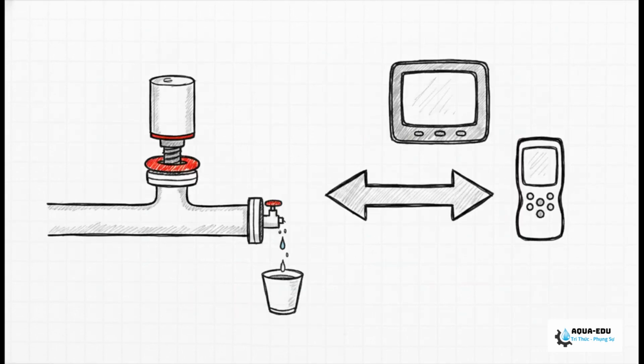Time to reinstall the probe securely into the stainless steel pipe T. Make sure your O-ring isn't torn, check for any leaks, and make sure there are no dead legs in the flow. Let the process flow resume and stabilize for a good 5 to 10 minutes. Once it's settled, pull a sample from the local sampling valve right next to the probe and immediately compare your online transmitter reading against your freshly calibrated handheld meter.